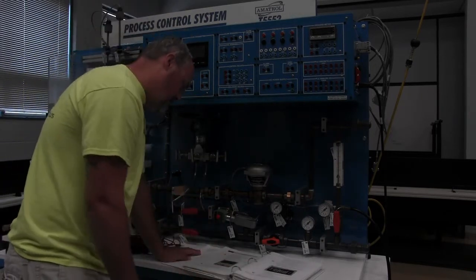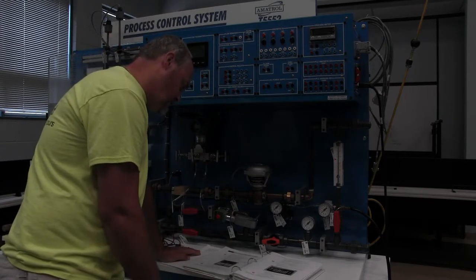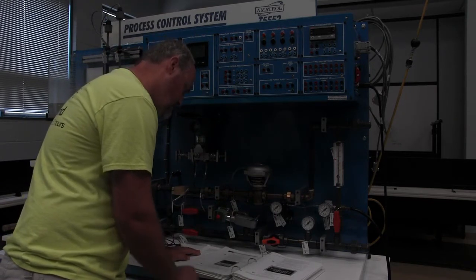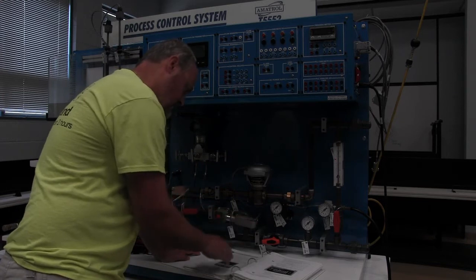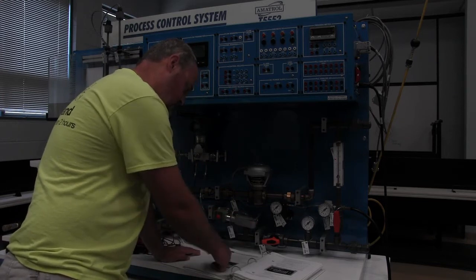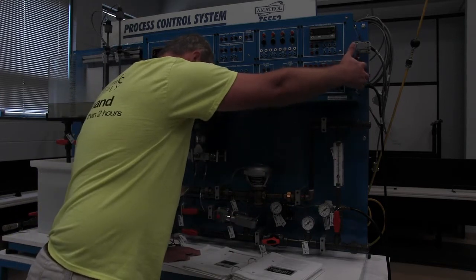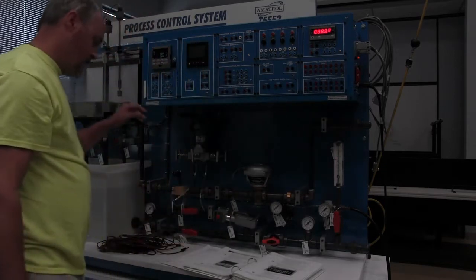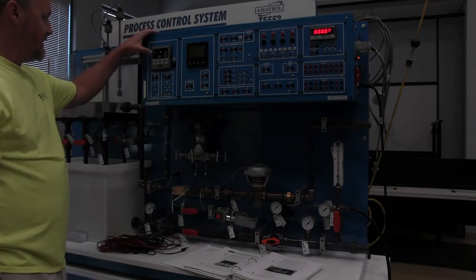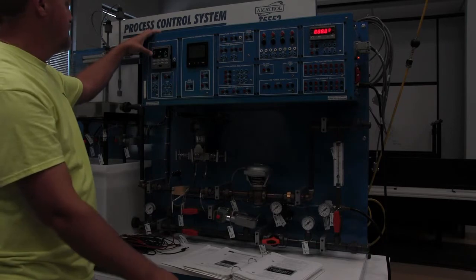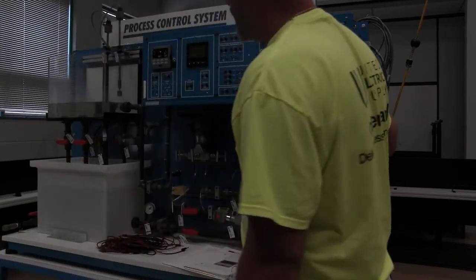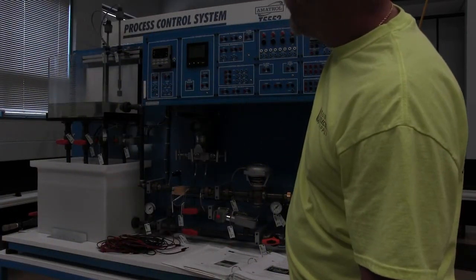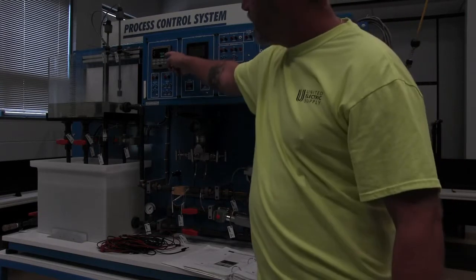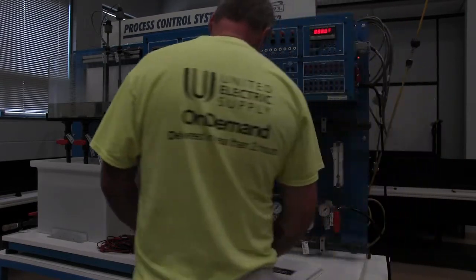So it says perform the following sub-steps to power up the controller and observe the display on the controller. Make sure the main power cord is plugged in. It is. We're going to go ahead and turn the breaker on and observe the controller. It should say test and then test done, which I believe I missed because it's pretty quick. I'm going to jump to this side. Test done. So that portion is good.